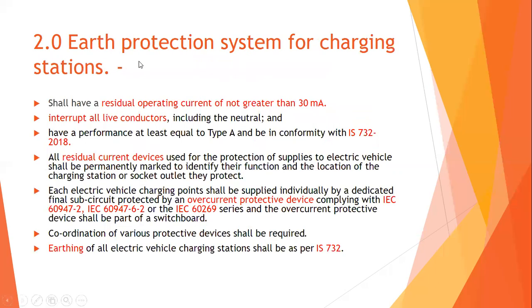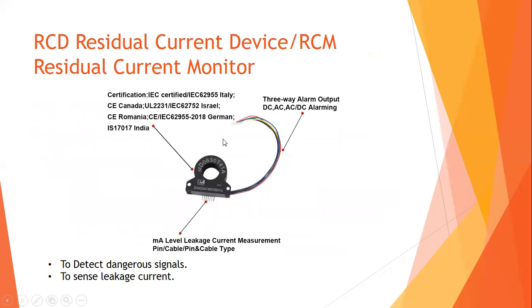Rule 2 covers the earth protection system for EV charging stations. The residual current device shall have a residual operating current of not greater than 30 milliamperes and shall interrupt all live conductors. It shall have performance at least equal to Type A in conformity with IS 732-2018. All residual current devices used for protection of supplies to electric vehicles shall be permanently marked to identify their functions and the location of the charging station or socket outlet.